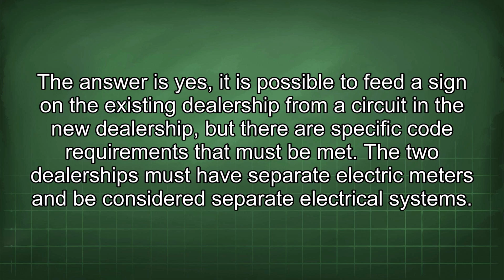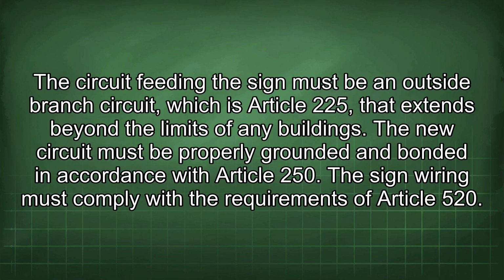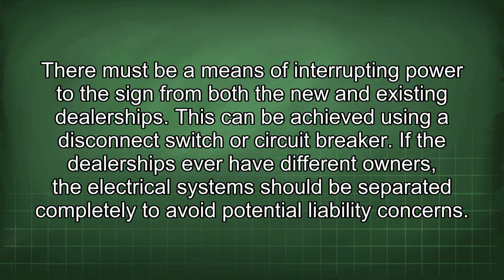The two dealerships must have separate electric meters and be considered separate electrical systems. The circuit feeding the sign must be an outside branch circuit, which is Article 225, that extends beyond the limits of any buildings. The new circuit must be properly grounded and bonded in accordance with Article 250. The sign wiring must comply with the requirements of Article 520. There must be a means of interrupting power to the sign from both the new and existing dealerships. This can be achieved using a disconnect switch or circuit breaker.